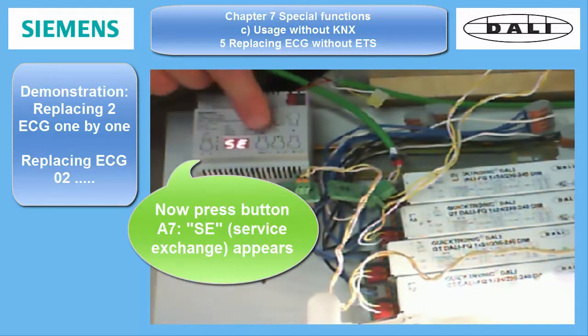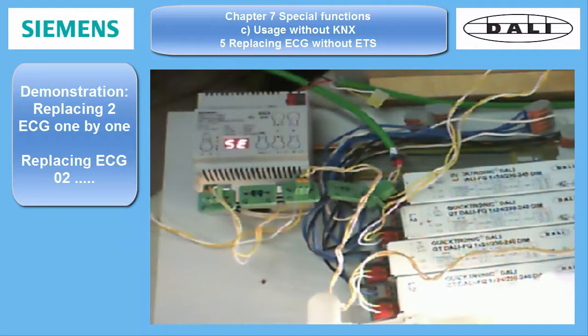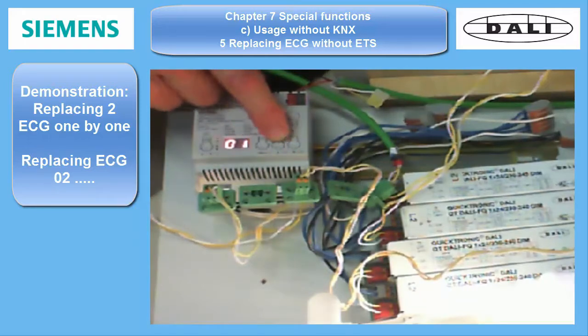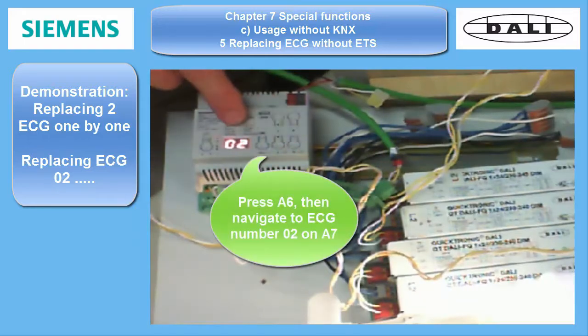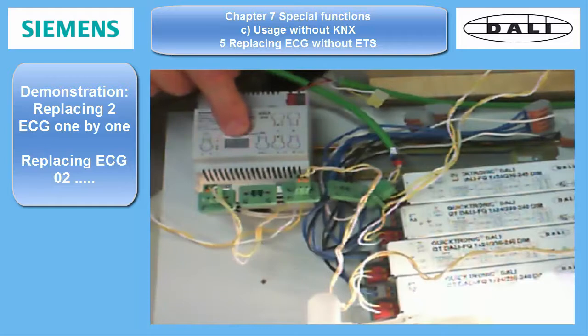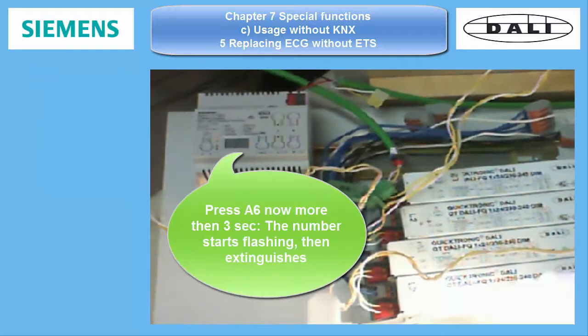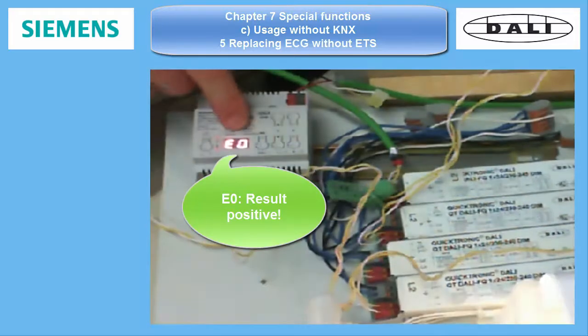Press A6 once, and the number of the first defective ECG is shown. With A7, you can navigate to other defective ECG, if there are any. When you have found the ECG you want to replace, you must press A6 long, more than 3 seconds. The number starts flashing in the display. After a while, E0 should be reported, which means successfully replaced.